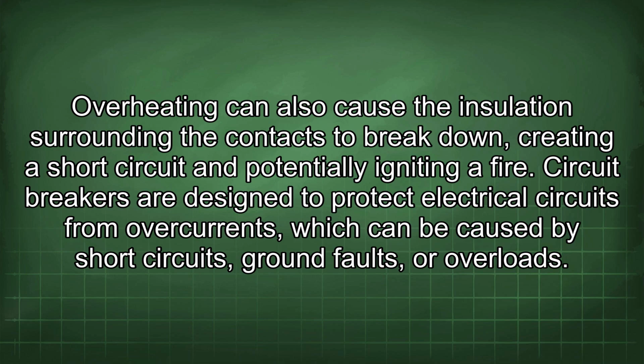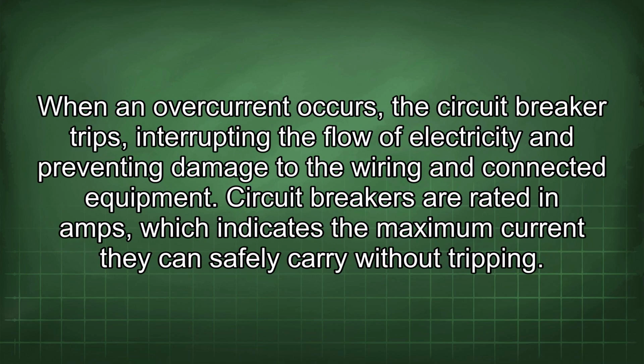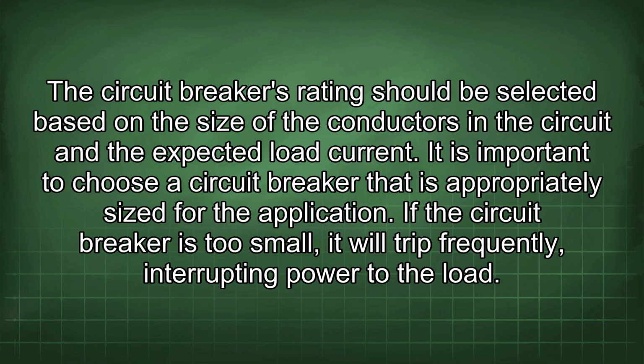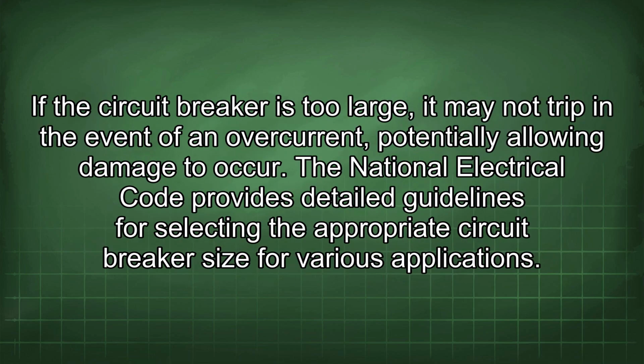Circuit breakers are designed to protect electrical circuits from overcurrents, which can be caused by short circuits, ground faults, or overloads. When an overcurrent occurs, the circuit breaker trips, interrupting the flow of electricity and preventing damage to the wiring and connected equipment. Circuit breakers are rated in amps, which indicates the maximum current they can safely carry without tripping. The circuit breaker's rating should be selected based on the size of the conductors in the circuit and the expected load current. It is important to choose a circuit breaker that is appropriately sized for the application. If the circuit breaker is too small, it will trip frequently, interrupting power to the load.